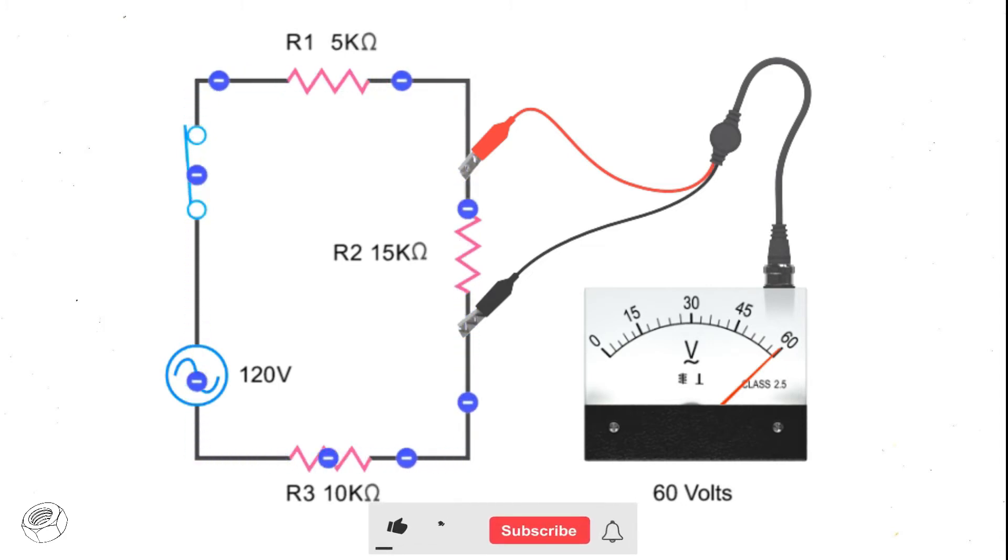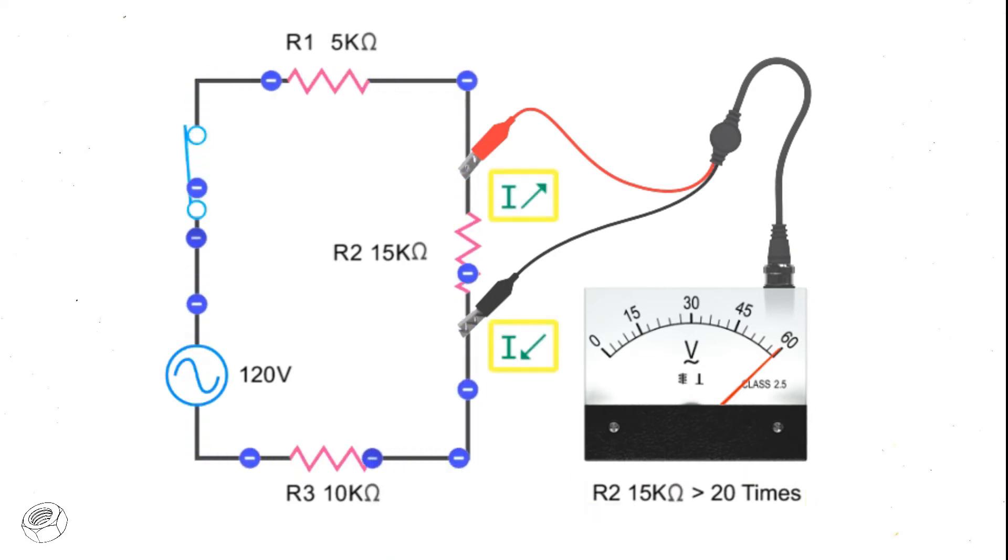If the voltmeter's internal resistance is less than 20 times the component's resistance, current will flow out of the circuit into the meter, resulting in an inaccurate voltage reading.